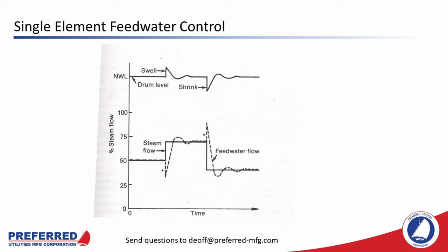There is a fundamental problem with feedwater control called shrink and swell. As steam flow out of the boiler increases, pressure in the boiler decreases, causing formation of more steam bubbles and the effective water level rises — we call this swell. The firing rate controller will also increase boiler heat input when it senses decreasing steam pressure, adding to the rising water level effect. A single-element feedwater control that only sees water level will respond to the high water swell by decreasing feedwater flow. The problem is that feedwater flow is decreasing while steam output is increasing, and when the swell effect ebbs, the water level can be well below set point. The opposite effect — shrink — happens on decreasing steam flow. This can be managed in fire tube boilers with proper PID loop tuning, but water tube boilers have much more shrink and swell and often need a more sophisticated control system.